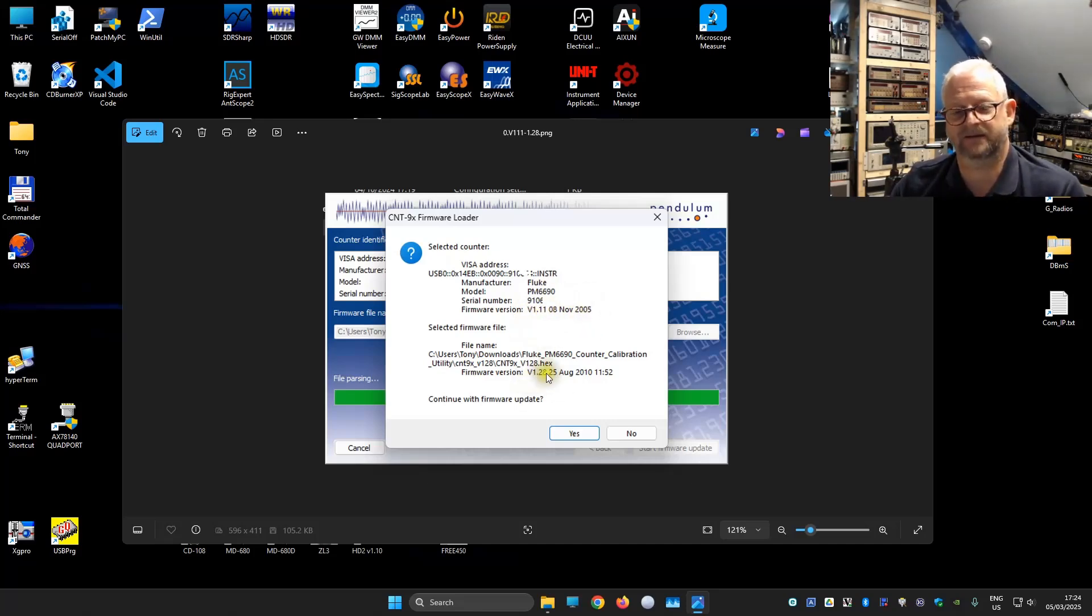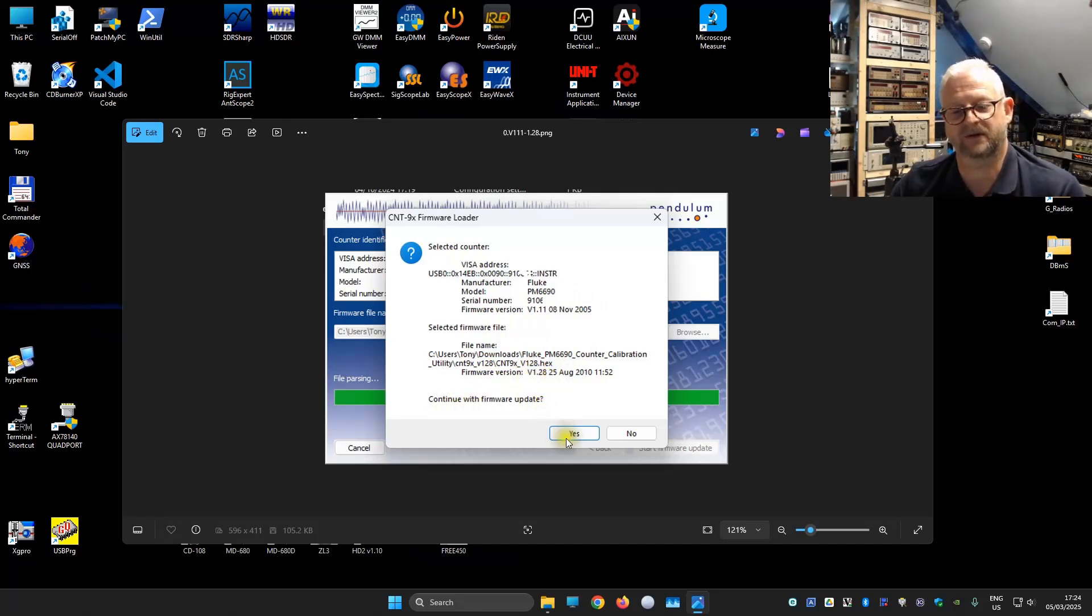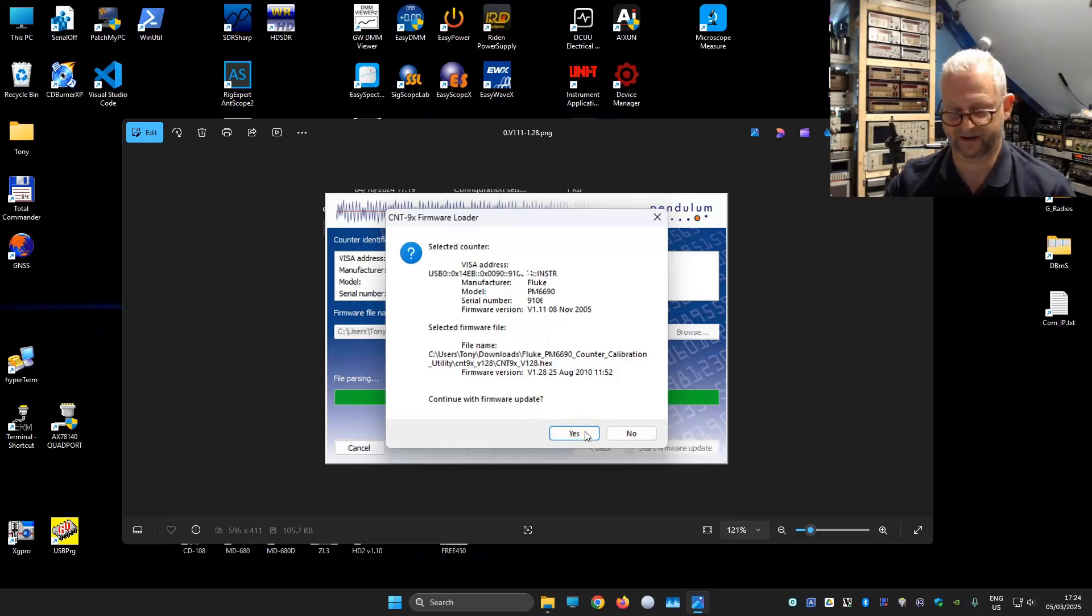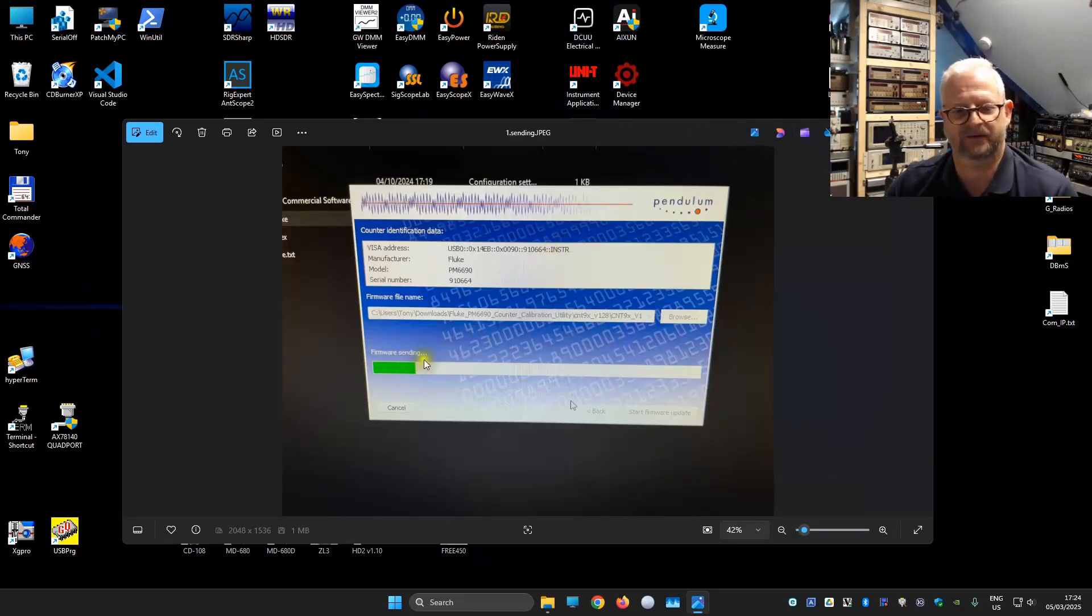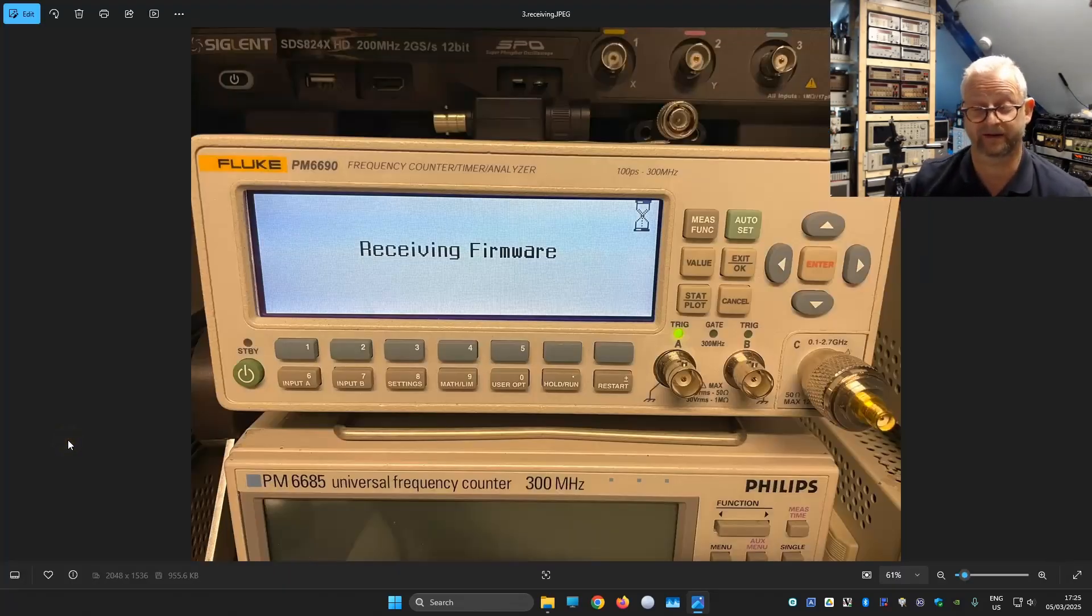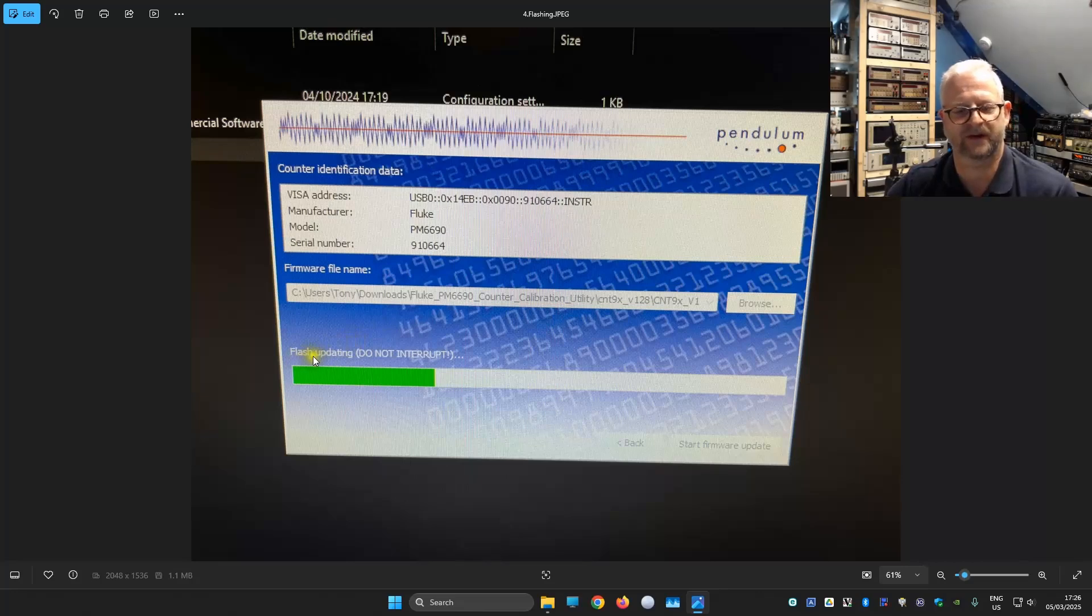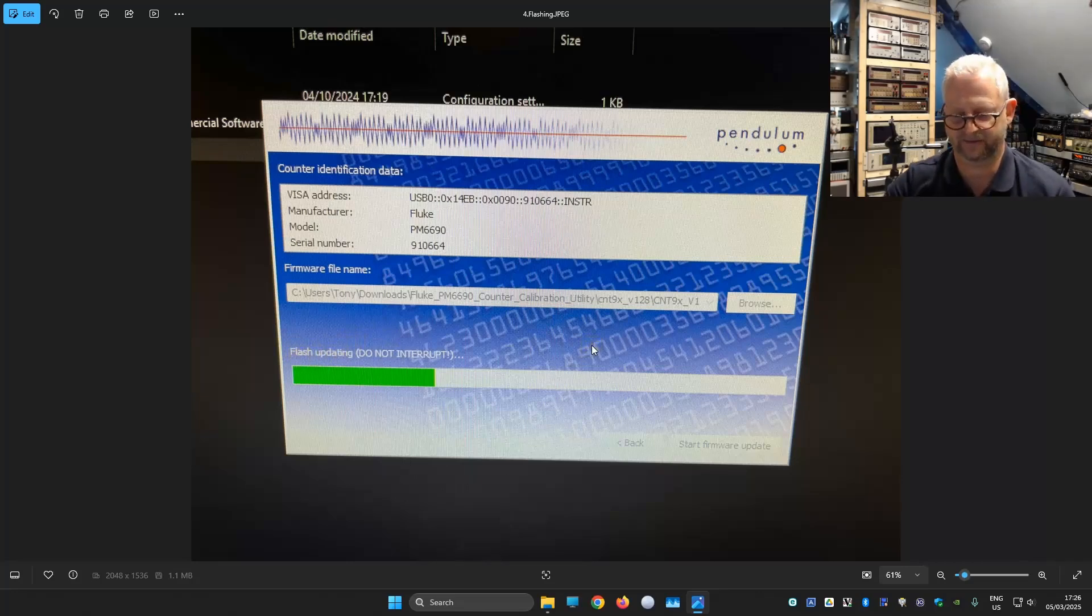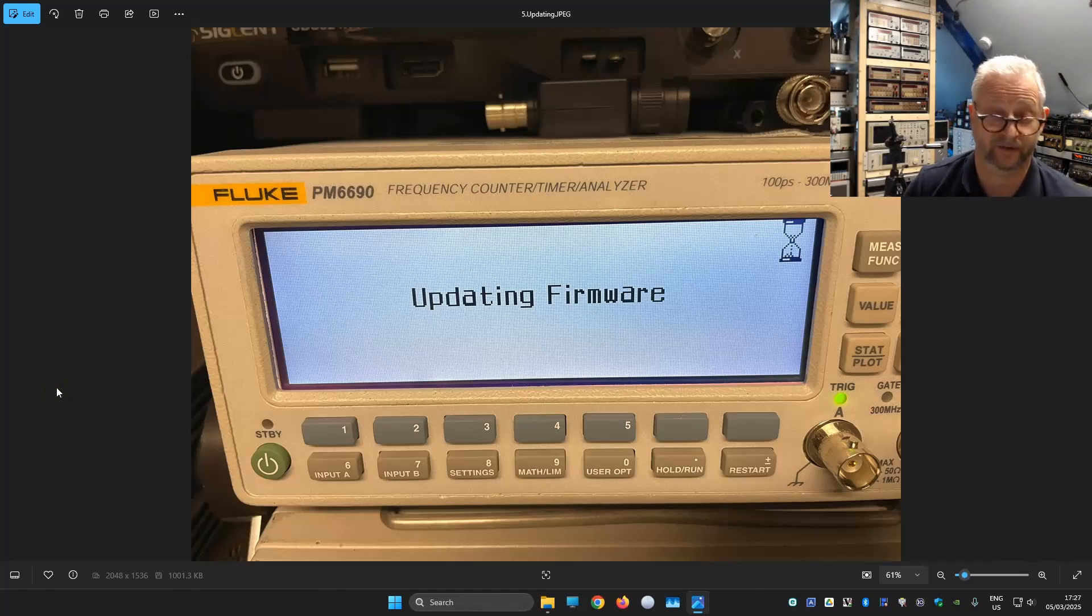The file I selected, it could also detect it is version 1.28. Do you want to continue with the update? And we can select yes. Now we see that it is sending the firmware file. In the display we see now it is receiving. After all the data is in the machine, it will change over the screen and it says flash updating. And in the screen of the counter we also see updating firmware.